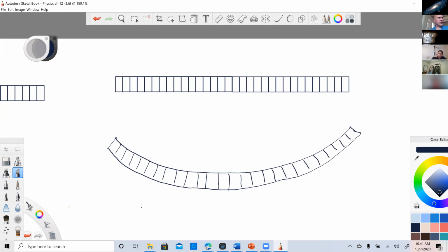Crystals, number and shape, 120 to 250. Once again, each crystal is about a wavelength in size. So far the same thing, same amount of crystals, about a wavelength in width. Some of these transducers have more than that, but that's fine, 120 to 250. Beam steering, some but not all the crystals are fired simultaneously.